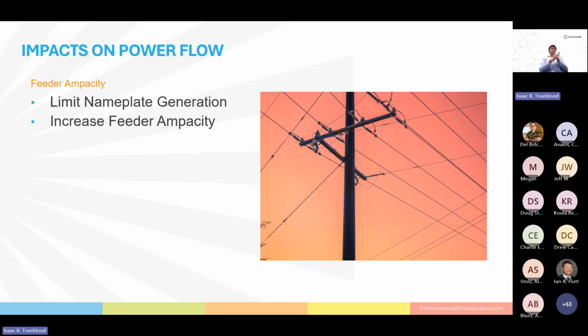Another impact of power flow is on feeder ampacity. In addition to backflows, distributed energy resources will often tie into the systems using the existing lines and feeders. This can cause issues with the amount of power the distributed energy resource generates exceeding the capabilities of the existing lines. Downstream of the distributed energy resource, also known as the load side, this will be a non-issue, as it doesn't increase the amount of power flowing to a load.